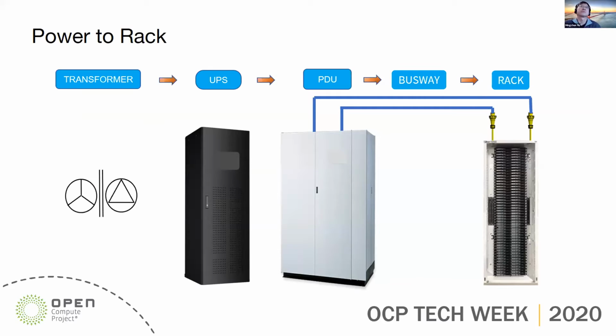This is a quick look at the power path for the Uber data centers. Like others, Uber also uses a three-phase transformer to convert the medium voltage to the low voltage for the data center building. We do use a traditional centralized UPS for backup. Following that, we deploy the PDU to further lower down the voltage and provide the power to the rack through the busway. Since we use the central UPS, we have a dual AC source to the rack, for power redundancy.